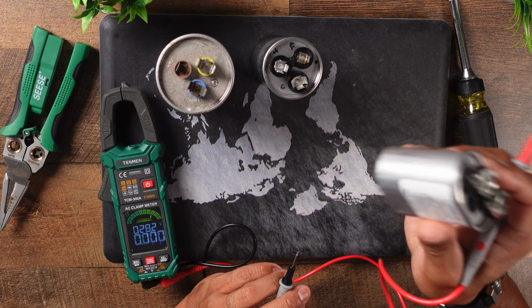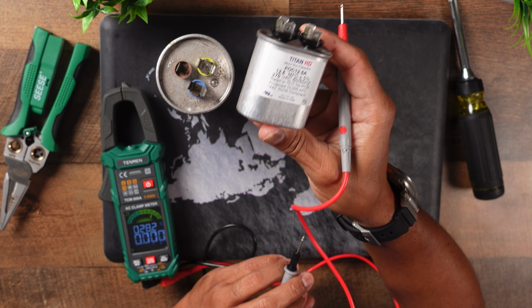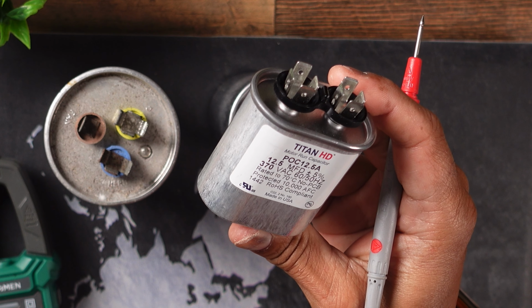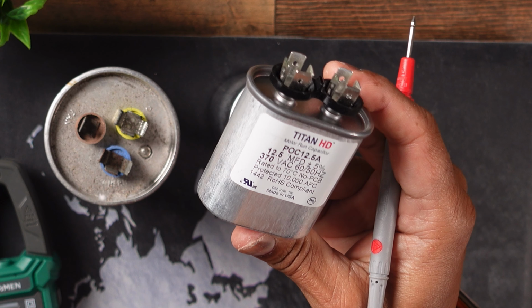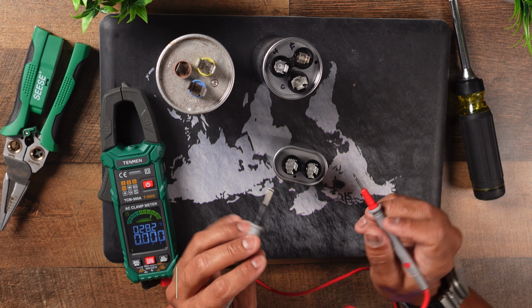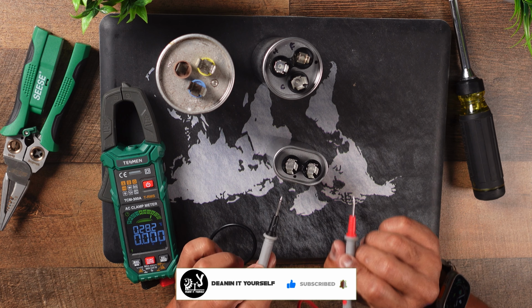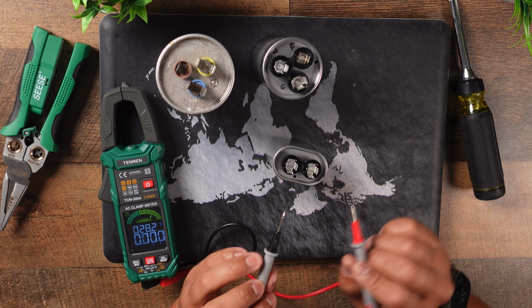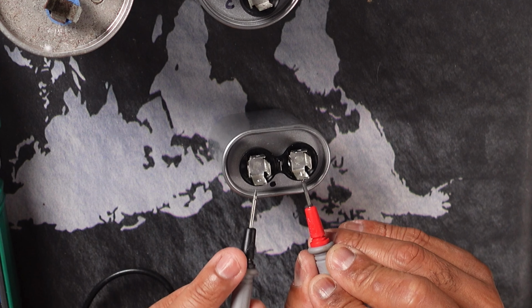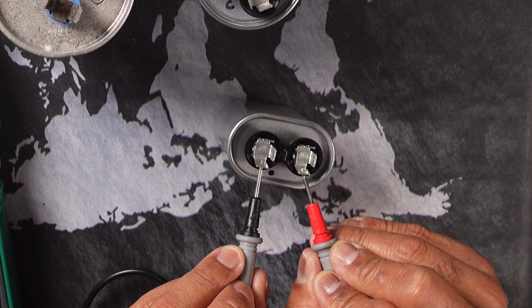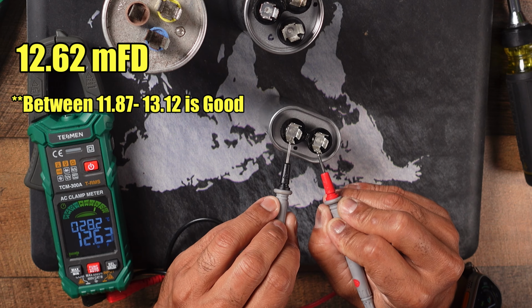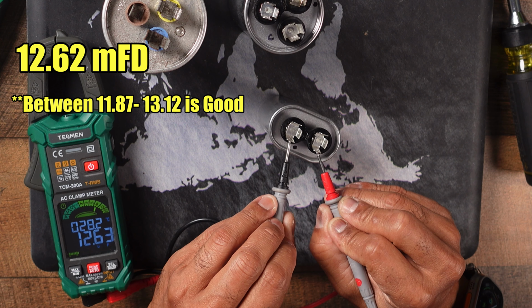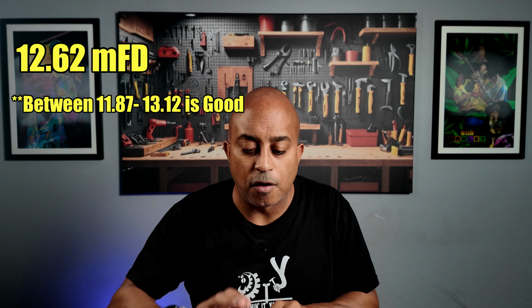If your capacitor only has two ports, like this one, take a look at the reading. Mine says 12.5 microfarad plus or minus 5%. Put your leads on either of the ports, it doesn't matter which terminal, but you're looking for 12.5. We'll wait for our meter to read, and like you see there, it's 12.62, which means this capacitor falls within the tolerance of being good.